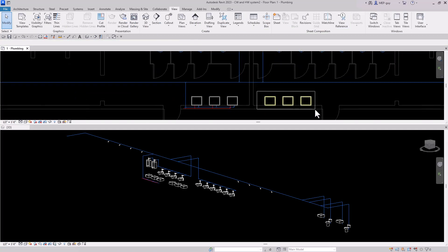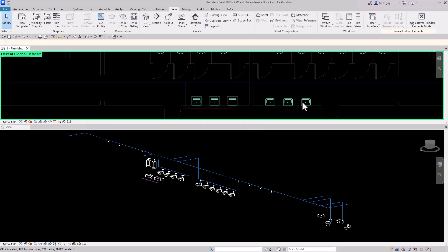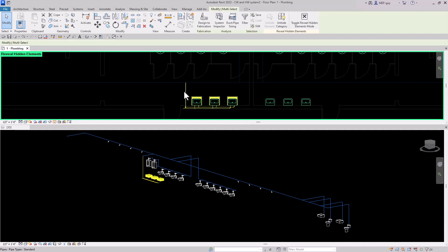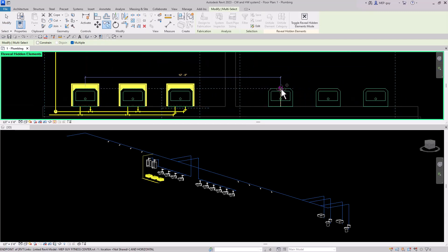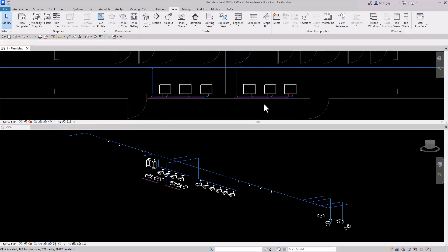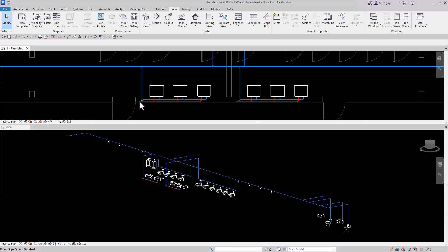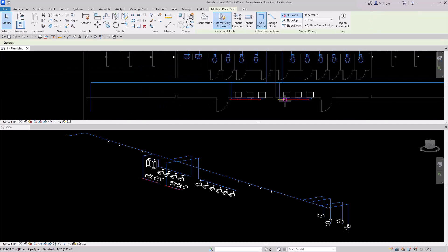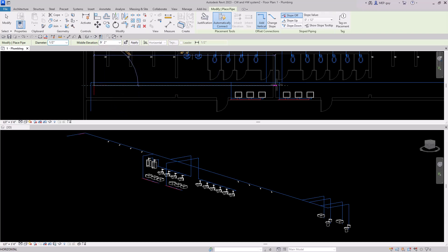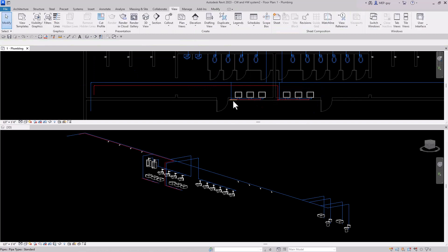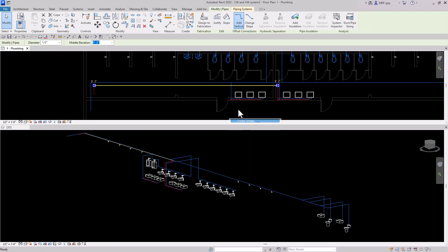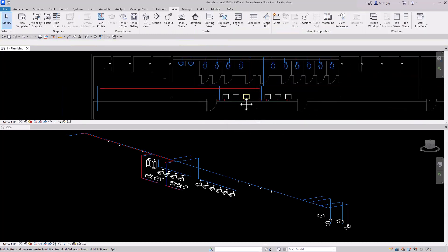So we have this set up, and I want to copy this over. I'm going to delete these, then I want to see where they exist, so I'm going to turn on the reveal hidden elements. I want to make all these piping connections, and we want to copy from maybe this fixture, so I'm going to use my keyboard shortcut for copy, and then we are going to copy it over to here just like that. Then I can turn off reveal hidden elements, and now I can make the connection to my main using the Trim Extend command. We have to bring these hot water lines up, so I'll use Create Similar, drawing at maybe 9'2", going from this point over, and it snaps nicely.